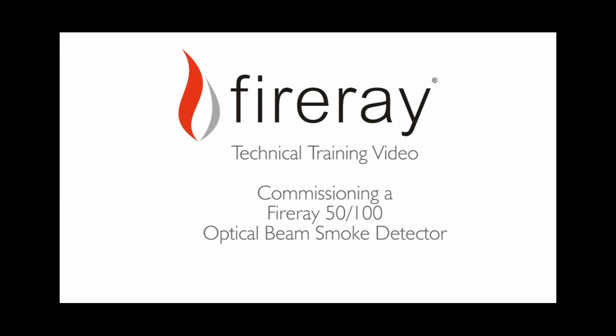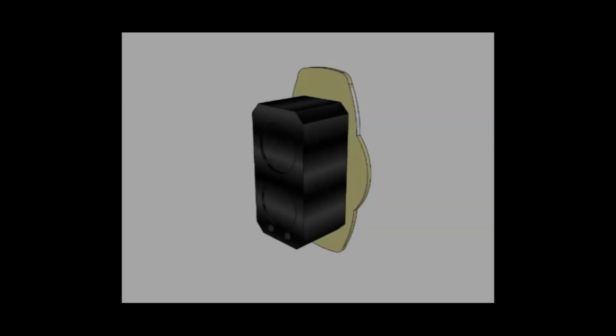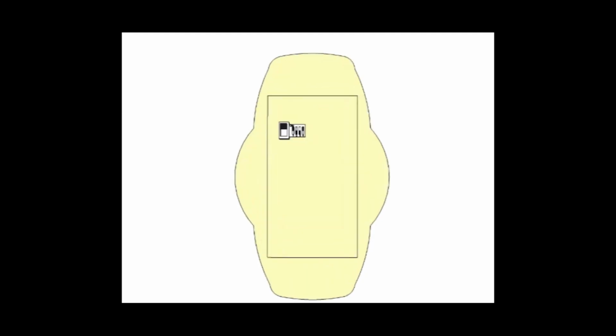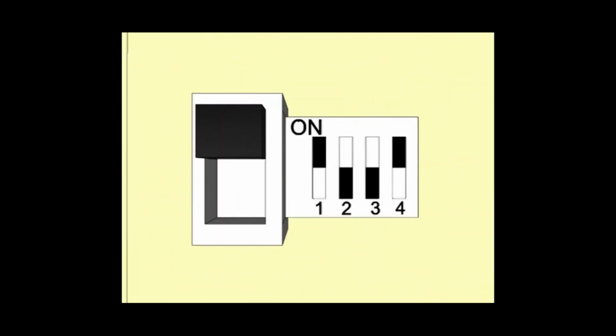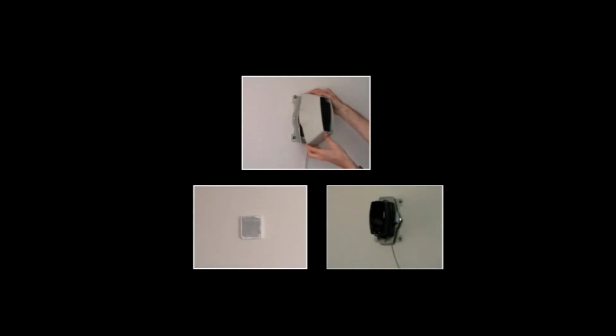Hello. I'd like to show you how to properly commission an optical beam smoke detector. The settings are given in the installation guide as well as on the back label of the beam detector. On the back of the beam detector are the dip switches and the mode switch. Choose the settings that you need. Factory default is switches 1 and 4 up and switches 2 and 3 down. The commissioning can be done with the front cover fitted or removed.